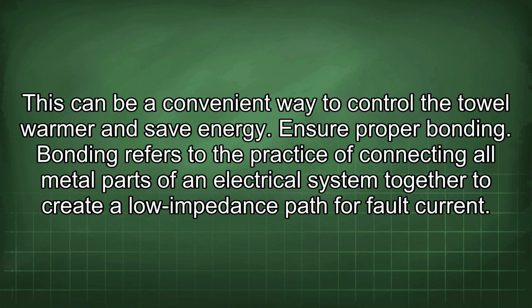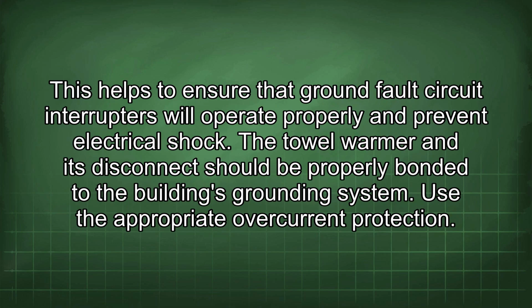Ensure proper bonding. Bonding refers to the practice of connecting all metal parts of an electrical system together to create a low impedance path for fault current. This helps to ensure that ground fault circuit interrupters will operate properly and prevent electrical shock. The towel warmer and its disconnect should be properly bonded to the building's grounding system.